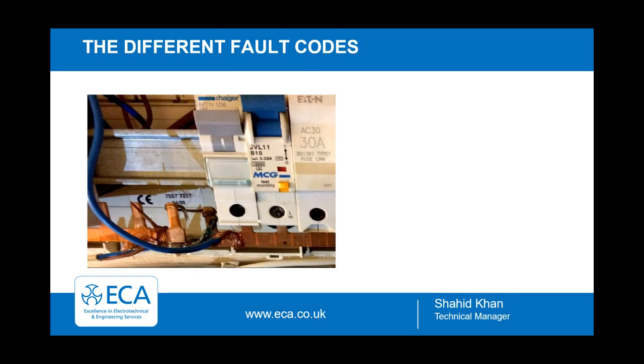Just Shahid, there's a point somebody's made. Would you put the worst code for multiple faults, or would you actually put a fault for each separately? Personally, I'd list every single fault. If there was multiple faults, I'd list each fault and code them appropriately. Even if the worst fault, when fixed, would solve the others? No, in that instance, you might as well just give it one. Give it the worst fault, and that's it. Yeah, in that instance, it'd just be the worst fault. Okay.